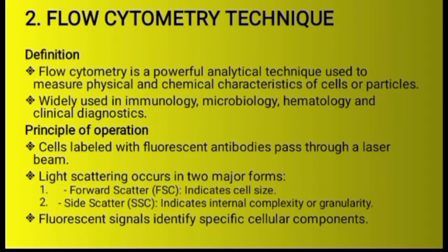However, in this case, the colors are not just physically seen, they are noticed by passing a laser beam forward scatter in such a way that it can measure the size of the cell, and also side scatter in such a way that the granules and the complexity of the cell can be noticed. So the granularity within the cell depends on the cell component within the cytoplasm of the cell.